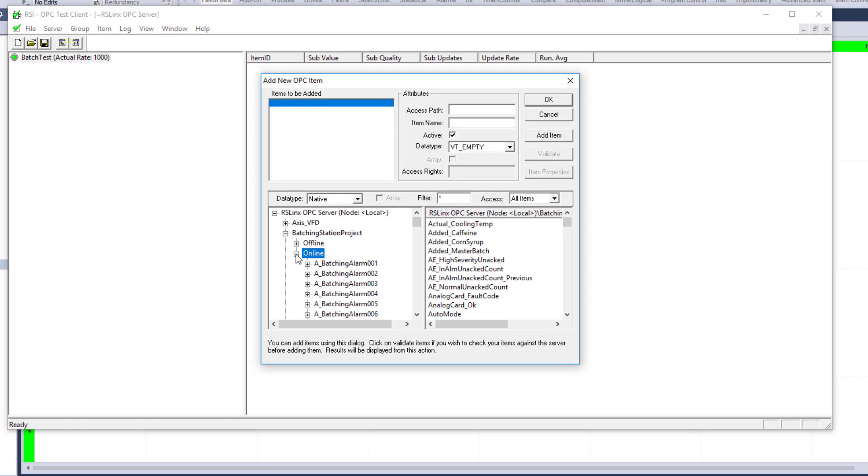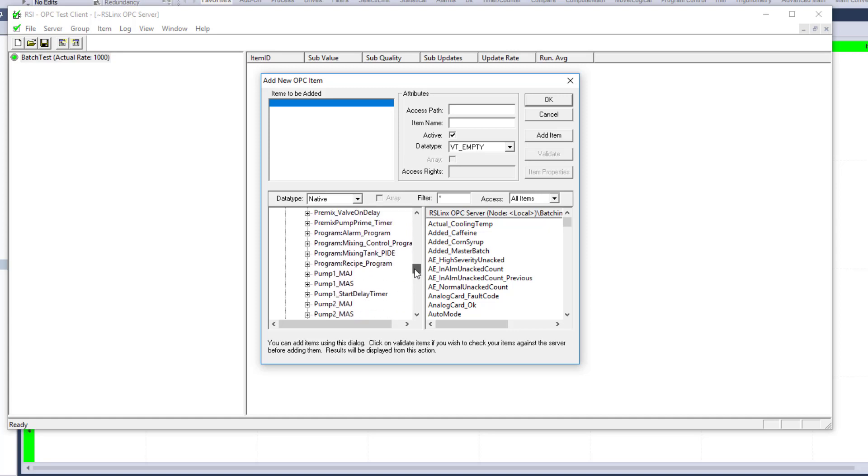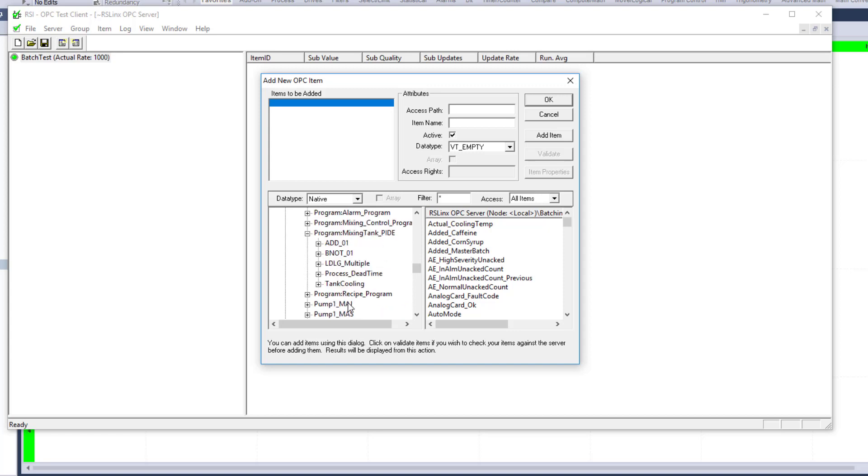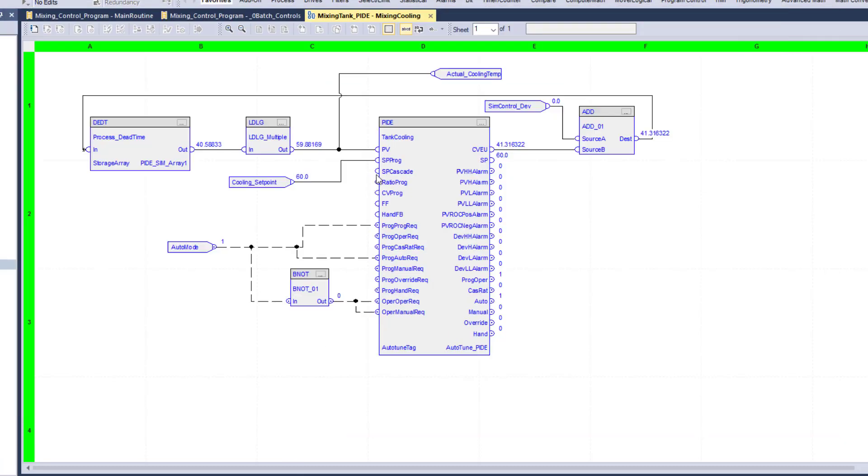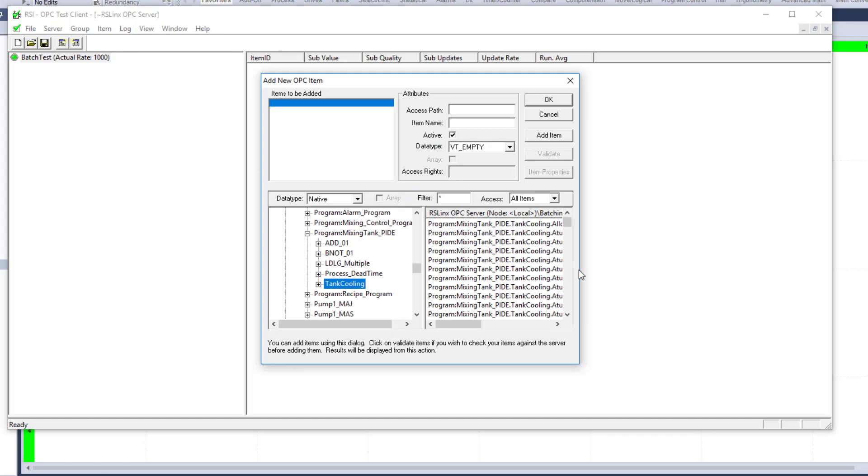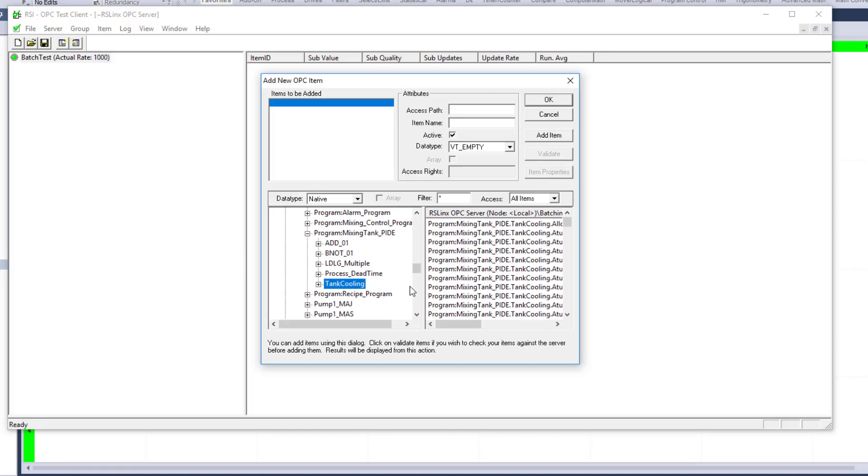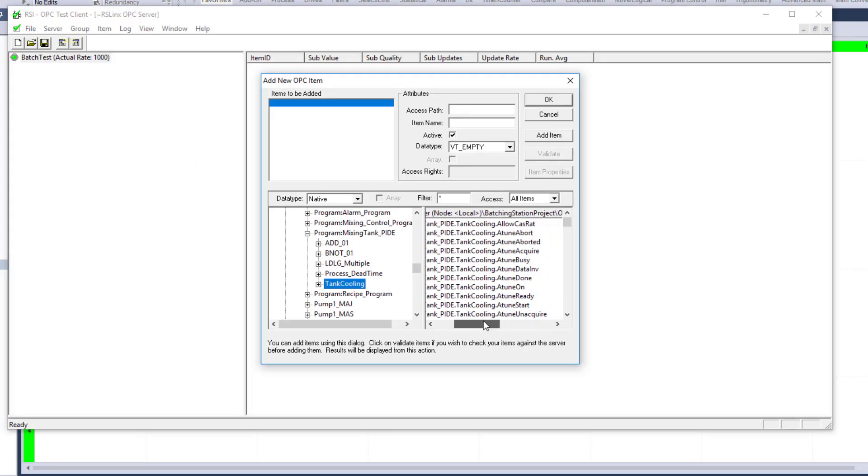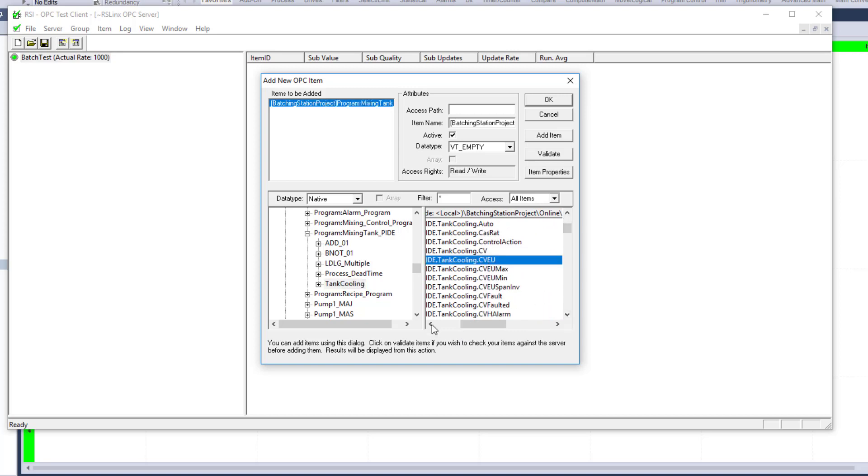So what we can do is go online, and then go down to our program levels. So we'll go down here, and keep in mind, it's called mixing tank underscore PID. So mixing tank underscore PID right here. This is what we want to get. So this is what we can click and actually find out where our PID is. Now our PID is actually called tank cooling. So we're going to grab that, and then we can grab whatever we want to inside of this. So in this case, we want to grab, let's just say the CVEU for that case. So the CVEU, come over here, and we'll come up here and find that tag right here.